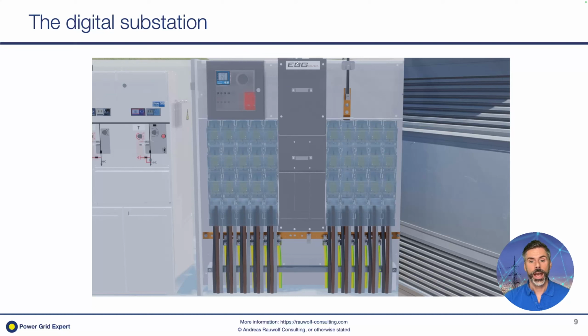In the low voltage compartment, we have here the supply from the transformer coming, and then this is distributed to the single feeders of the low voltage compartment. That's not visible, so behind those housings there are bus bars. So the single feeders are here, here, here, and they consist normally of three fuses. The fuses are a little bit hard to see, but you see these yellowish cubes, and exactly that is fuse number one, fuse number two, fuse number three. So these fuses are protecting those low voltage cables going to the houses, to industrial customers, to whichever customer. We have, of course, the three-phase and the neutral and the earth.